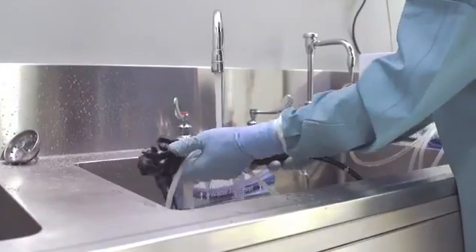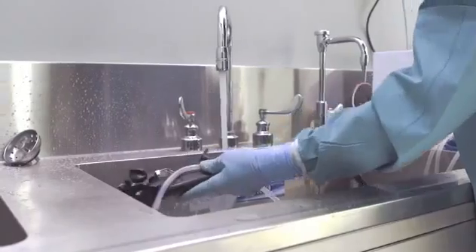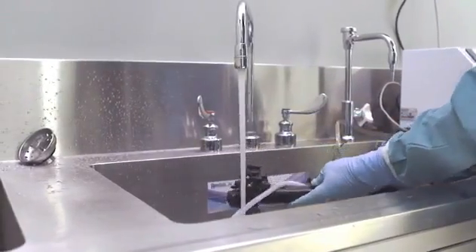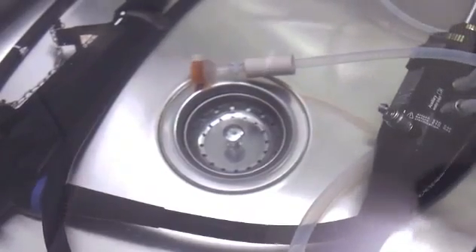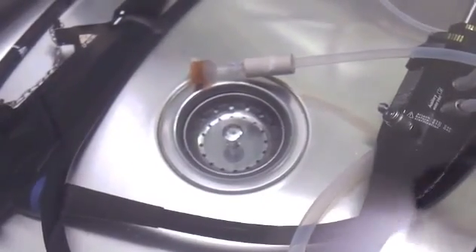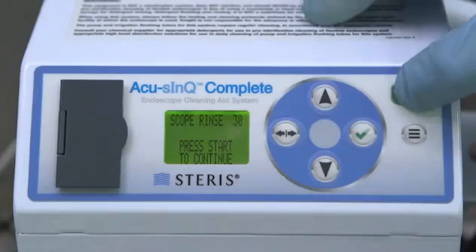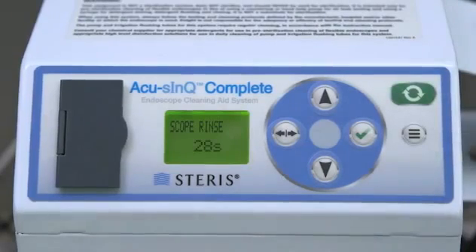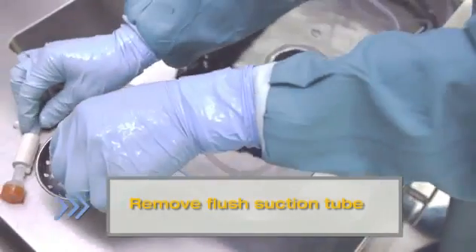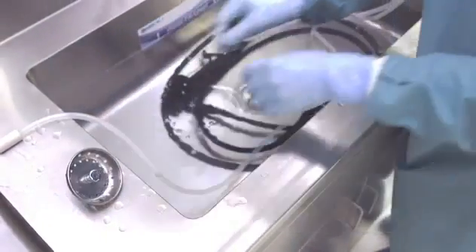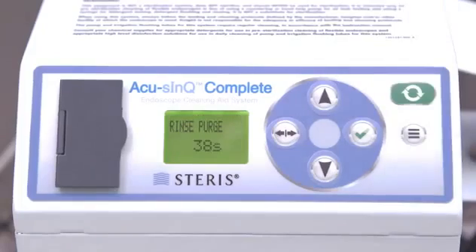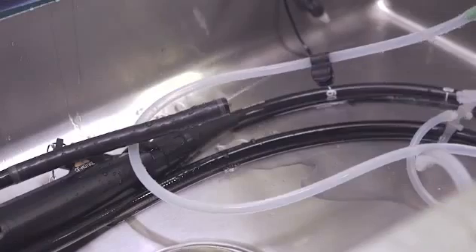Drain the sink and refill with fresh water to indicated level. Immerse the scope in the sink and confirm the flush suction tube is in the fresh water. Press Start to begin rinsing detergent from scope and allow the timer to count down to 0. Next, drain the sink and remove flush suction tube from water and place on the counter. Press Start to purge water from endoscope and let timer count down to 0.